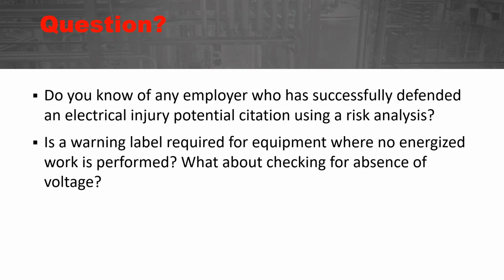7D, it says in 130.5H, the section for equipment labeling, and it says electrical equipment such as, and now this is not an all-inclusive list, switchboards, panel boards, industrial control panels, meter socket enclosures, and motor control centers, that are in other than dwellings. Well, it doesn't apply to dwellings. Here it applies to that type of equipment. Again, not an all-inclusive list, but how does it apply?